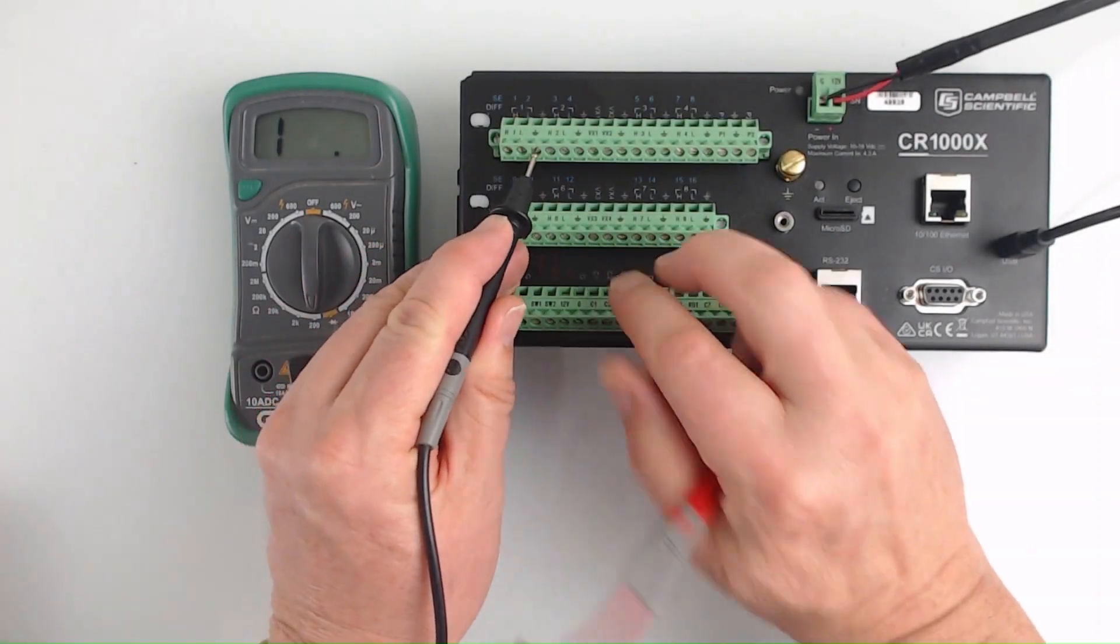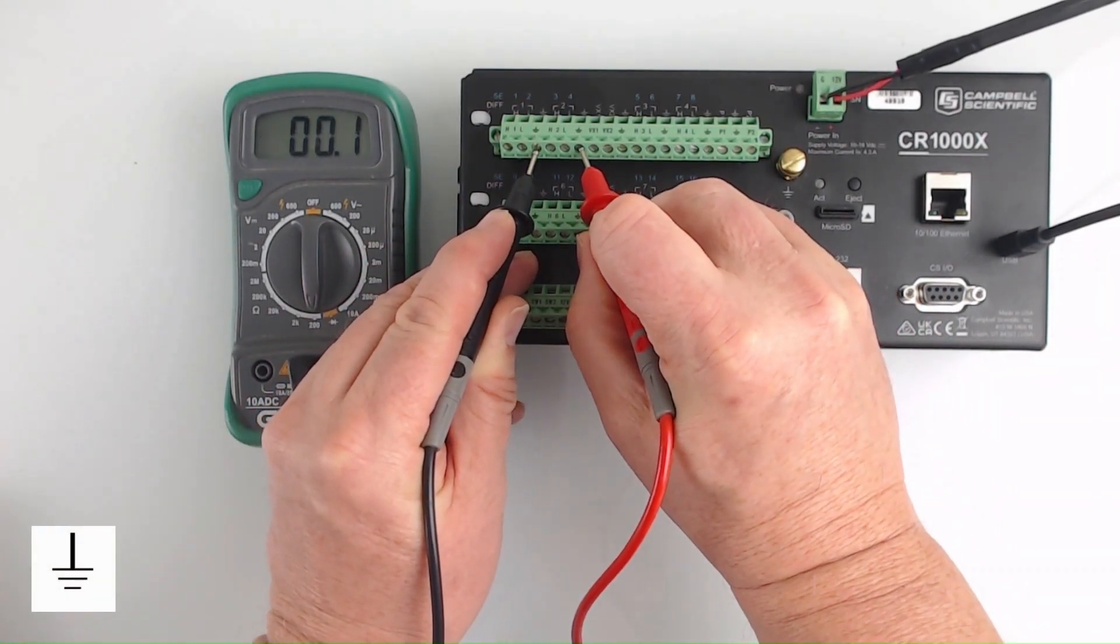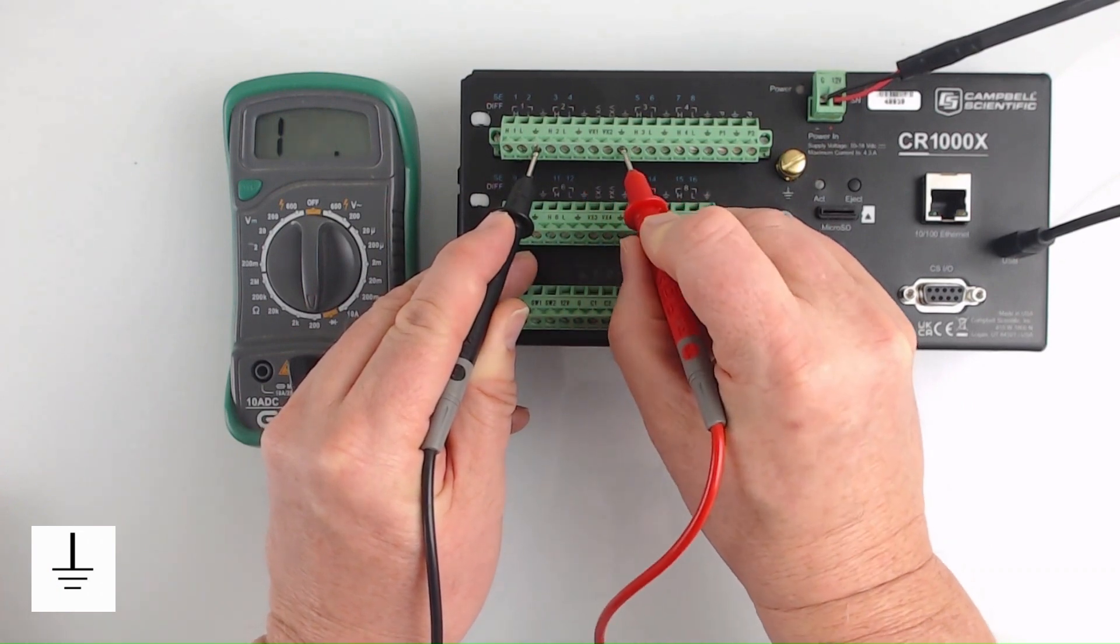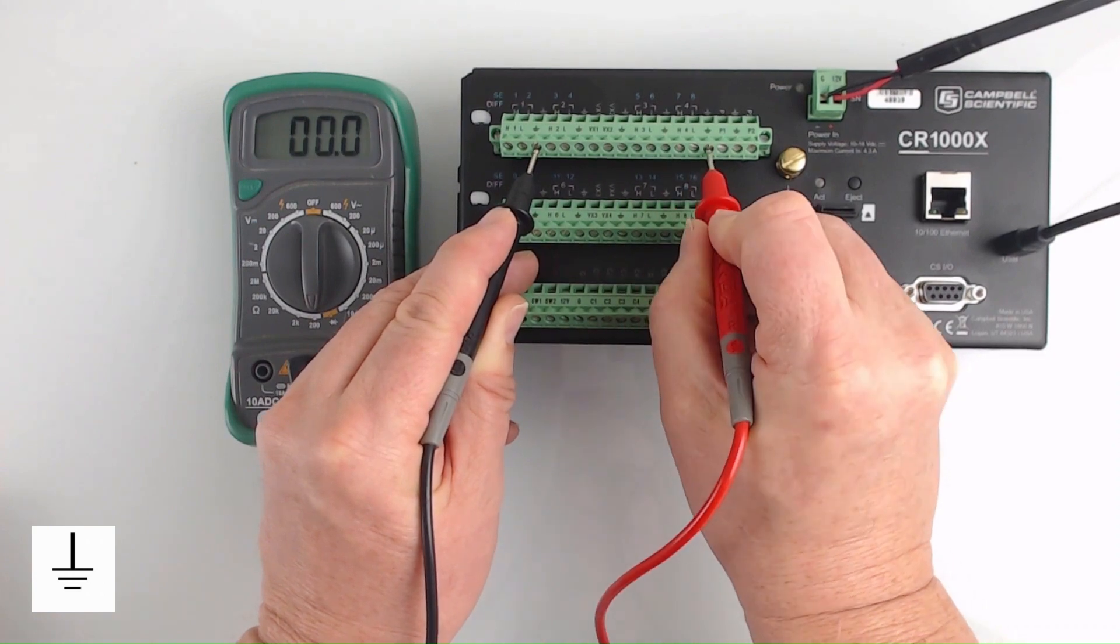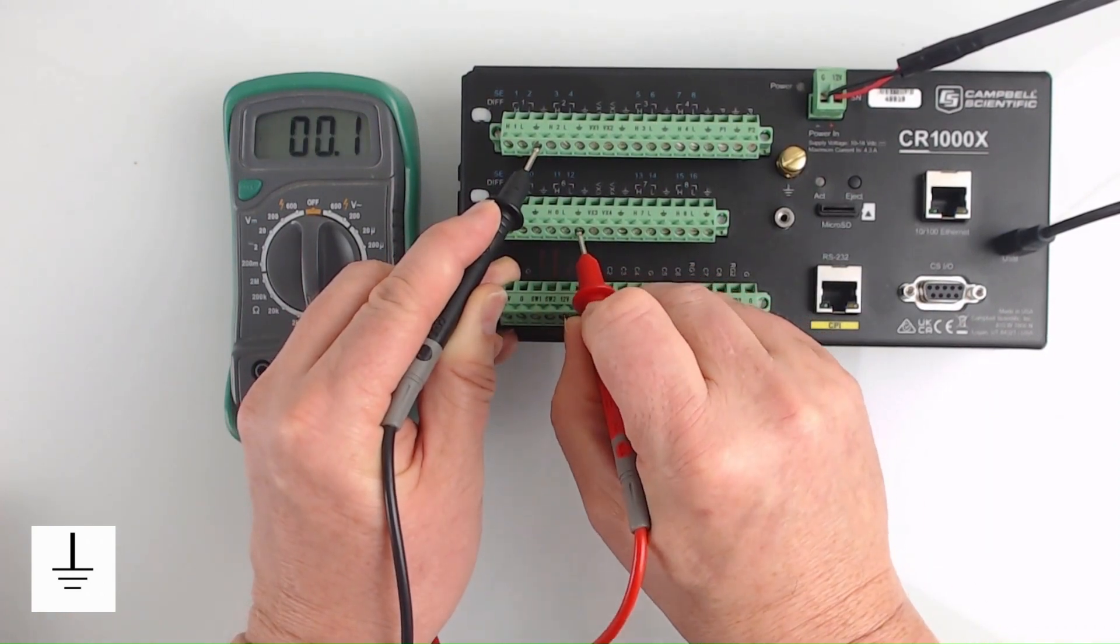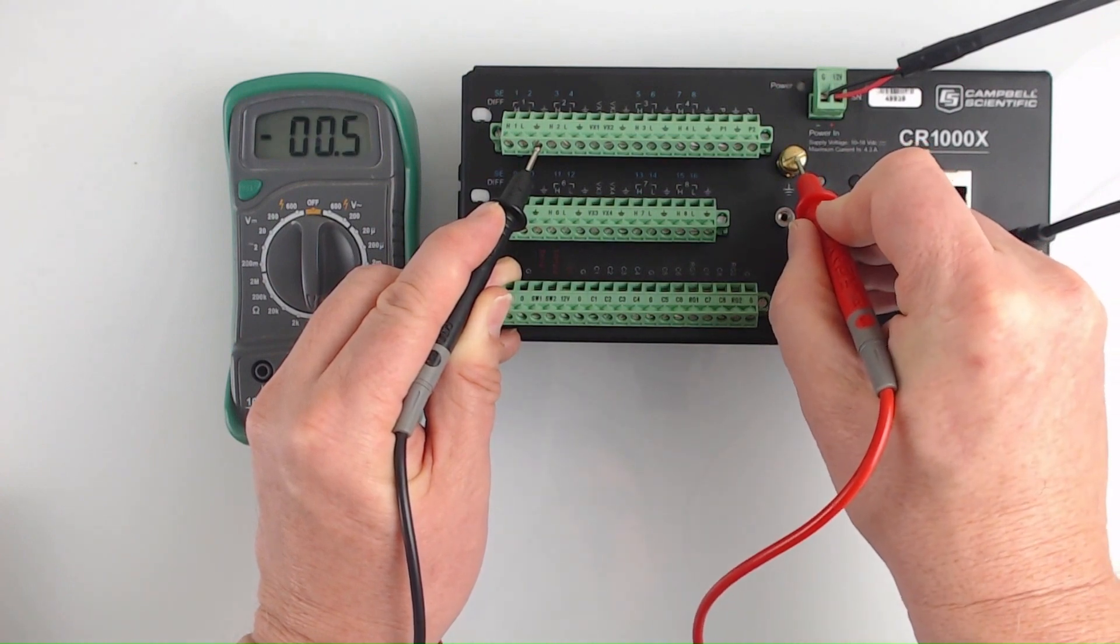Now we are ready to measure continuity. The datalogger has several channels labeled with this symbol. This is the signal ground, sometimes called signal return or analog ground. All of these channels are connected to each other inside the datalogger wiring panel. They are also connected to the ground lug.